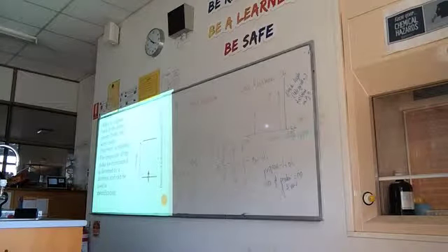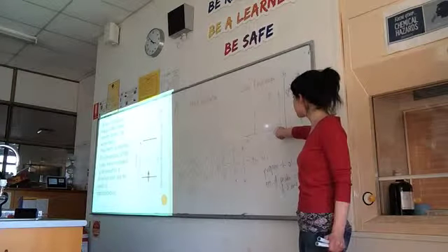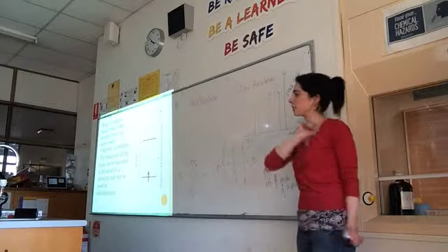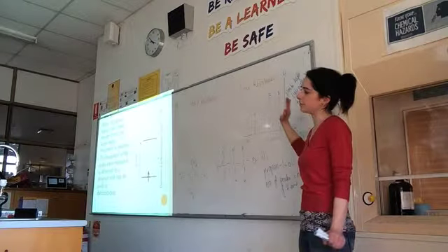To calibrate it, yeah. We want to make sure, so think about it. That gap is controlled by your magnet strength, your external magnetic field strength. From machine to machine, you're going to have different strengths. It's going to be very hard to get the exact same strength. So to standardize it, because each machine is different, every machine has to calibrate with TMS and give it a value of 0, so that these gaps stay the same between machines. Why TMS in particular? Because it's got high shielding and it will be really far away from anything else.